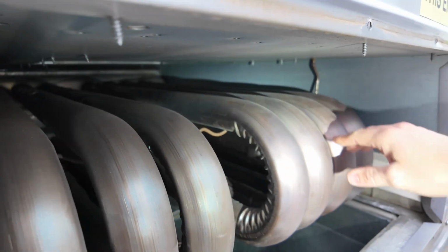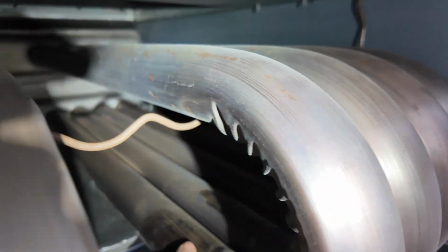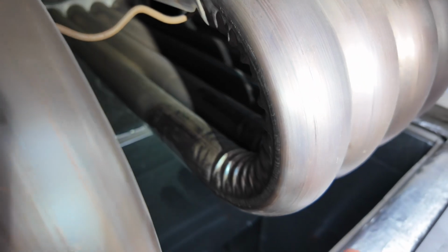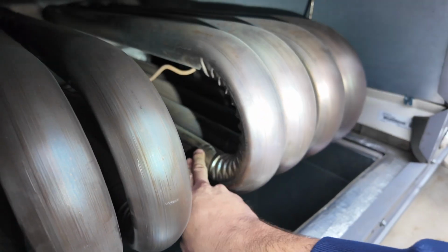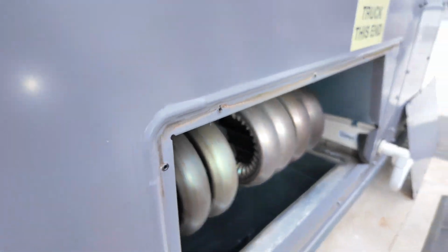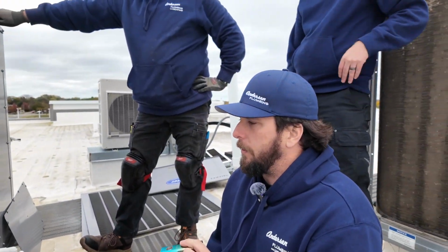So these tubes start out life as a straight piece of tubular steel. They are a seamed tube. So if you see that seam right there, basically they start life as a flat piece of metal and then it's rolled over and it's welded. So those seams are also a super common failure point because that's where the pipe was fused together originally.